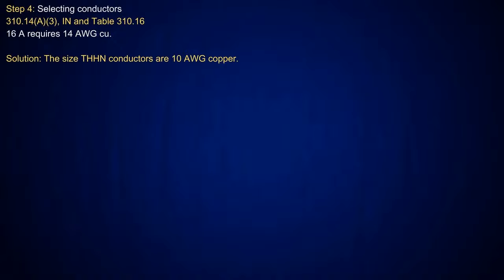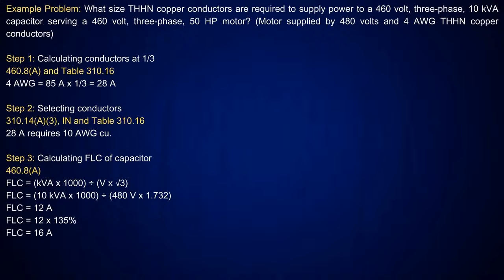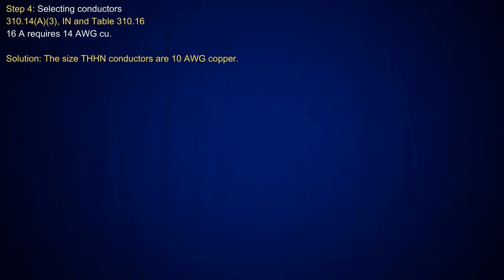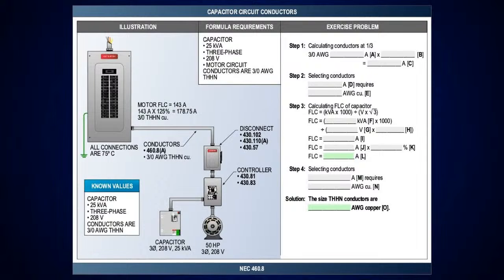If I go back, you're saying 16 amps requires a 14. But you're going off the 75 degree C column, right? Yeah. Okay. And then when you come here and look, which was the largest between the two? Well, it's where I calculated the conductors at a third. Gotcha. So therefore, the answer for this particular one going over to that capacitor is going to require me to have number 10 copper conductors. A lot of people have never seen that calculation. That's a new one. And we go through all this, like we did in the illustration here.